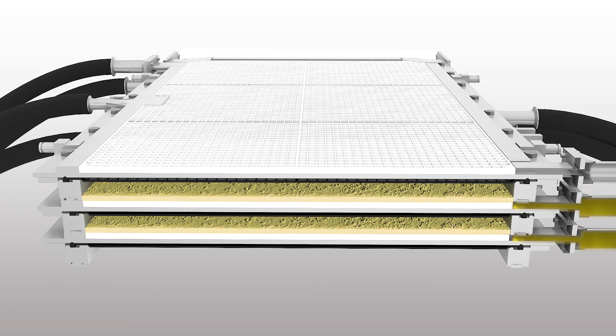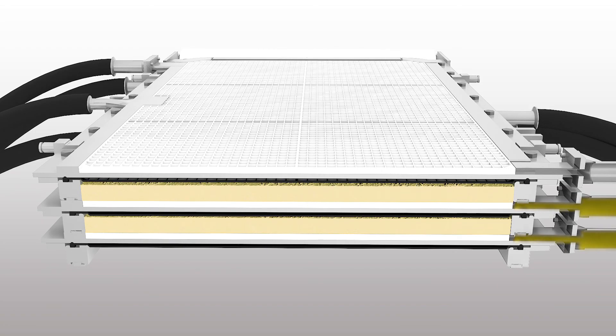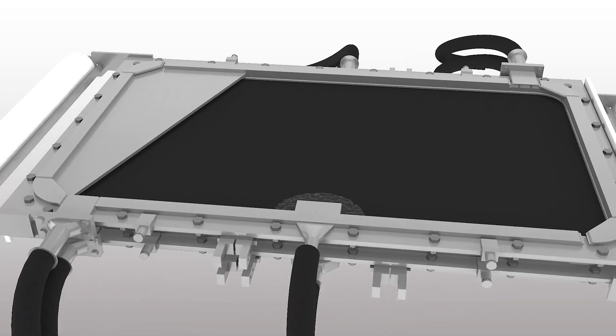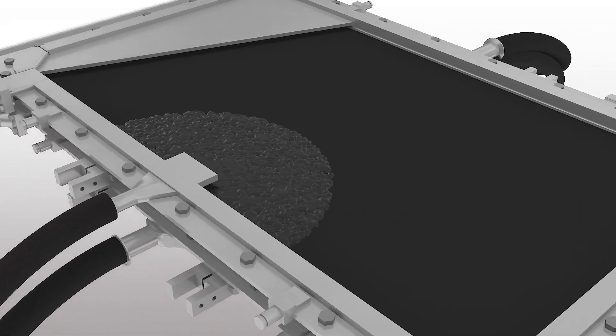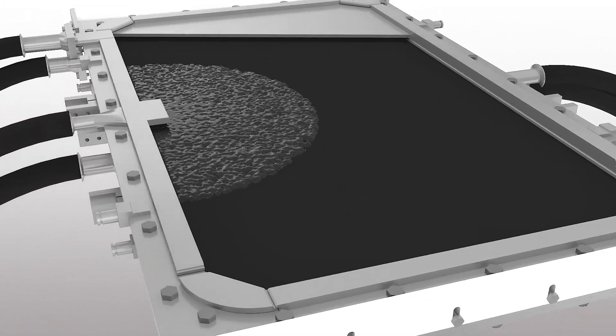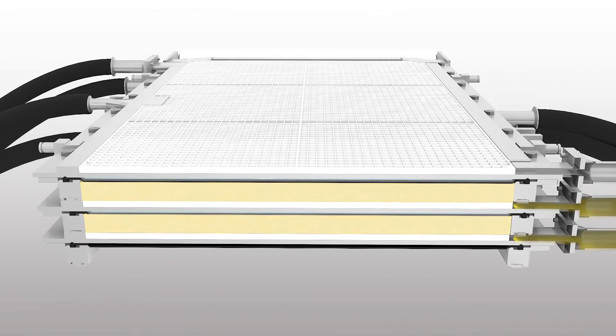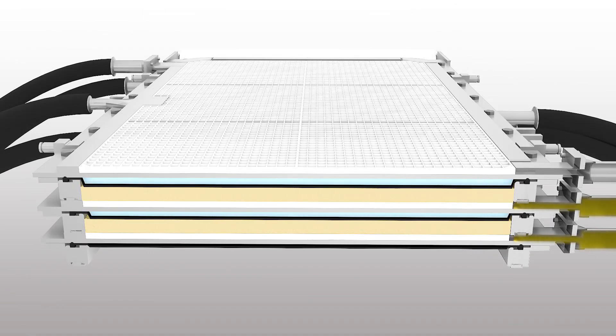The slurry header is drained. Pre-squeeze water enters through a water header into individual filter plates to squeeze the slurry up to 6 bar through hose pipes.